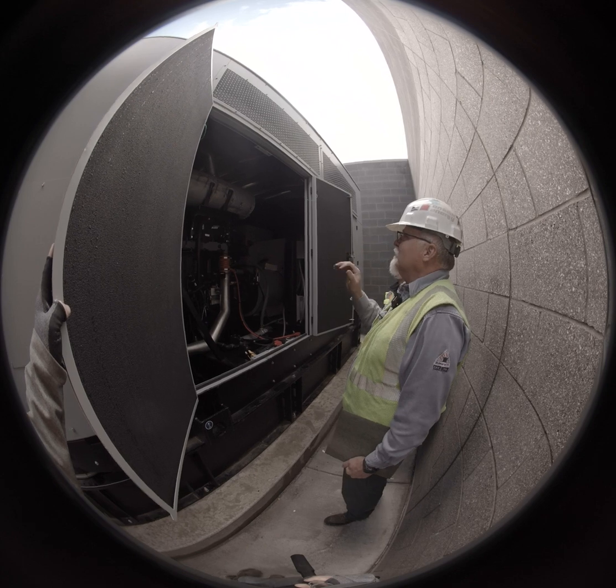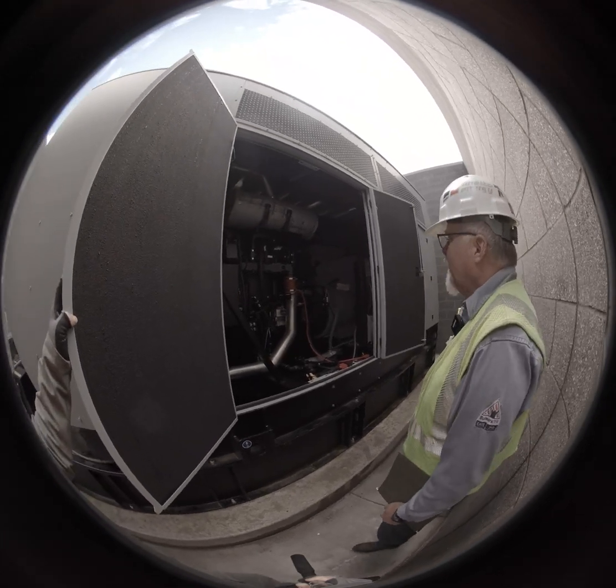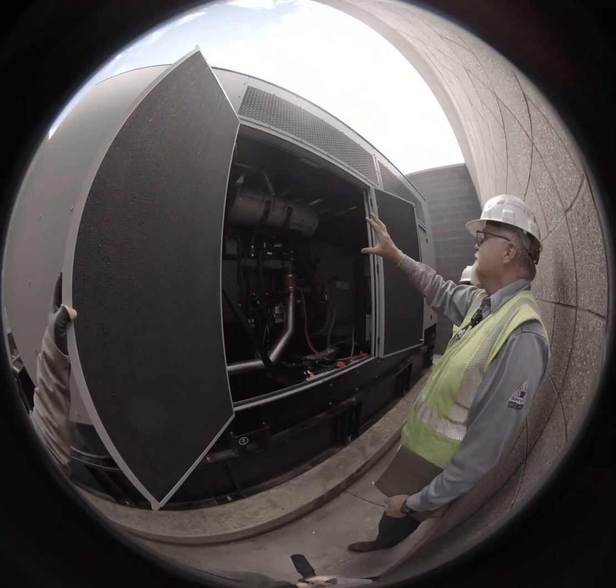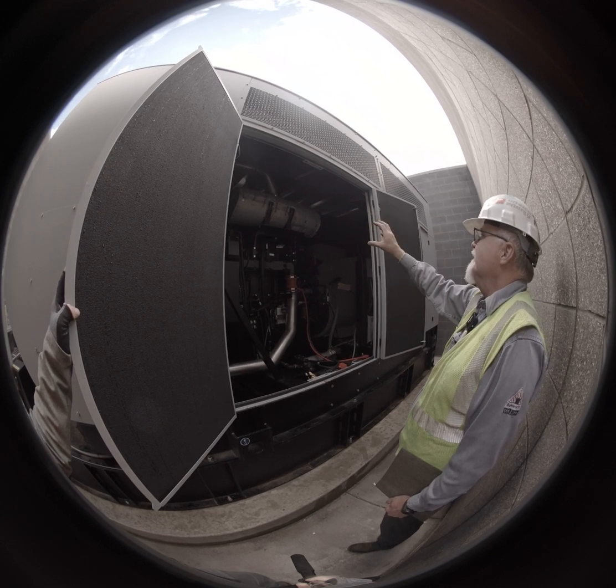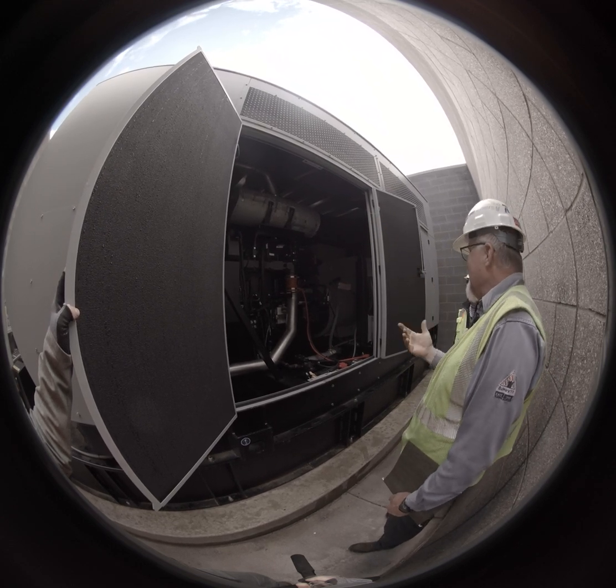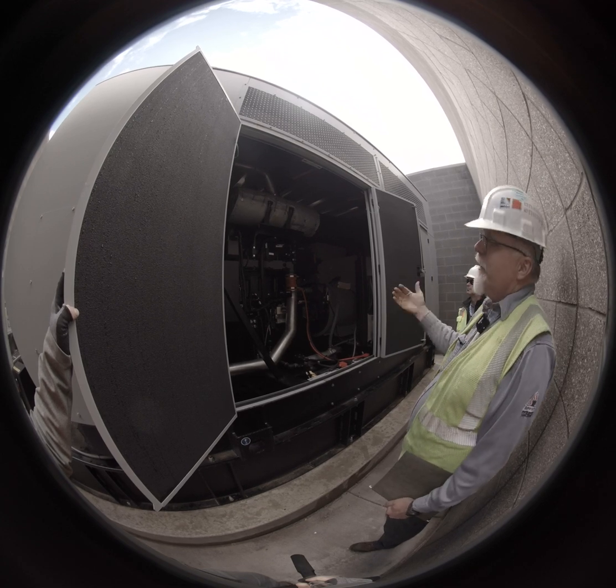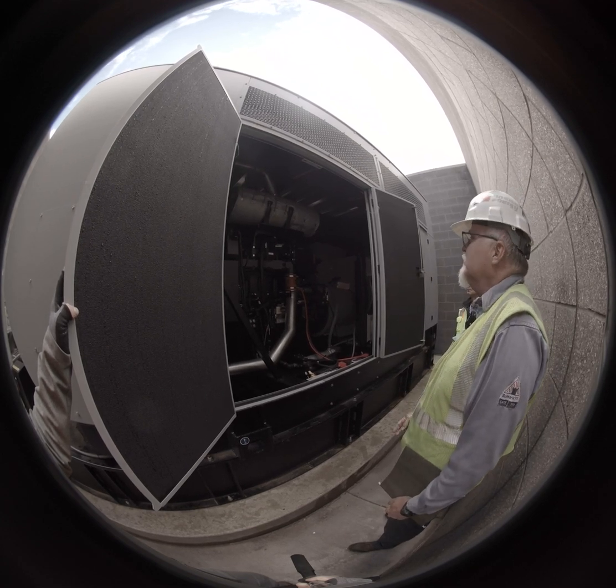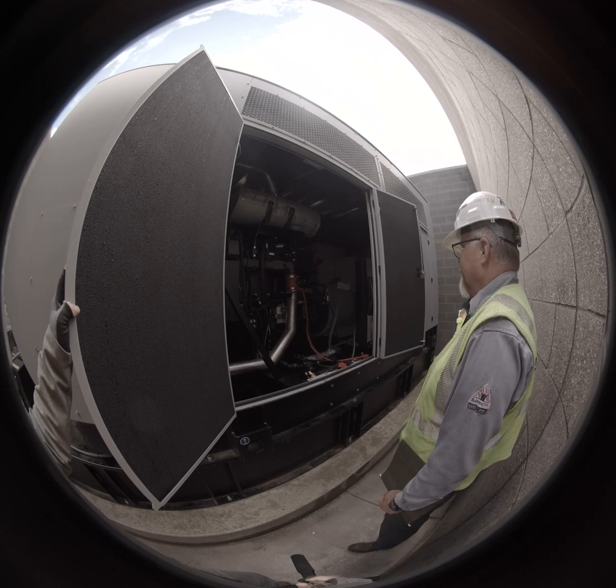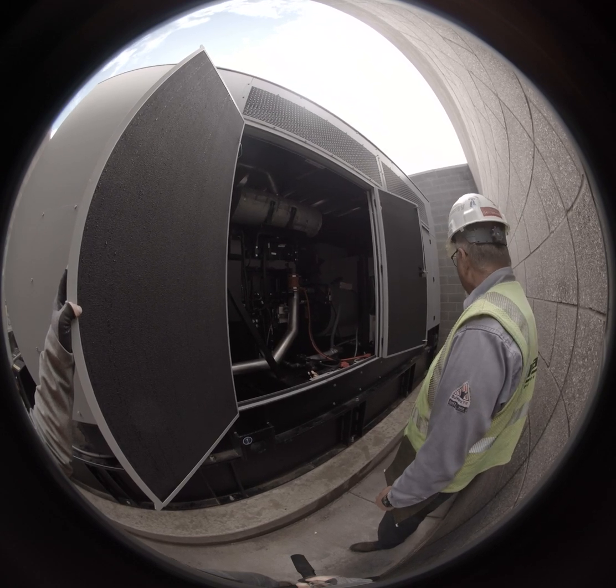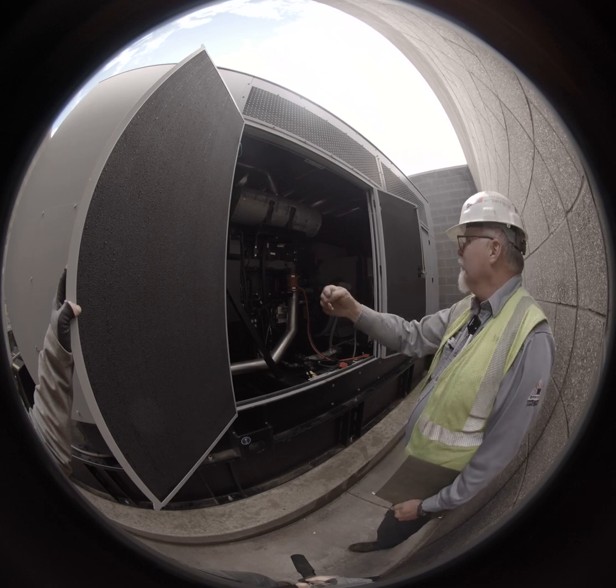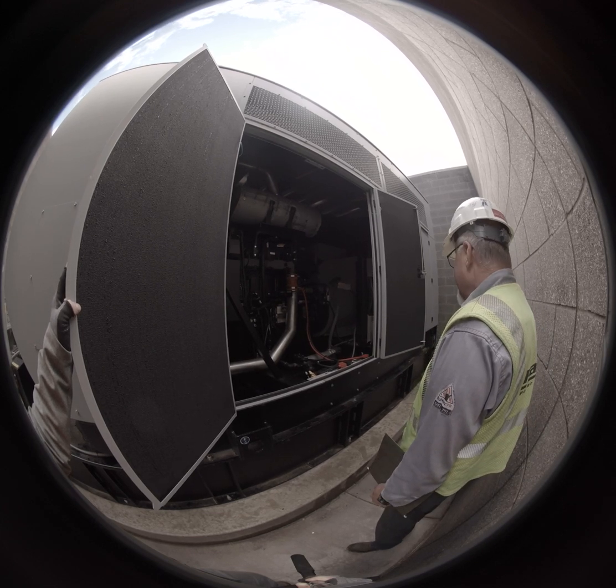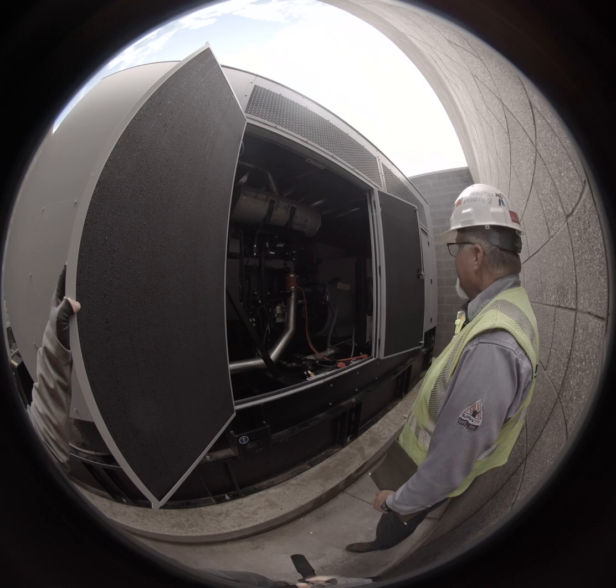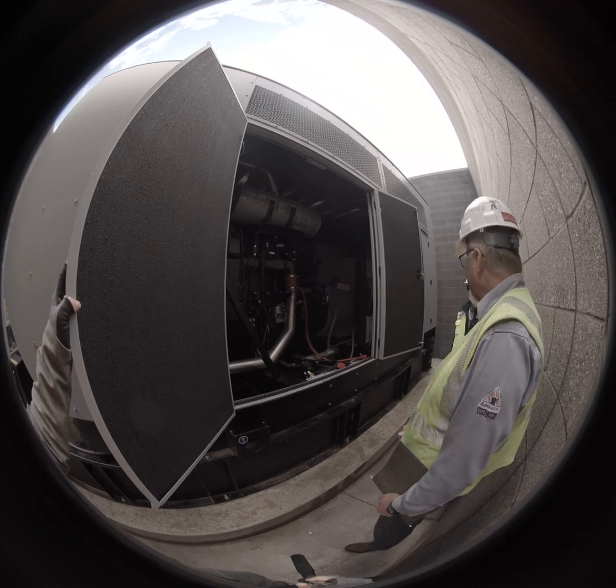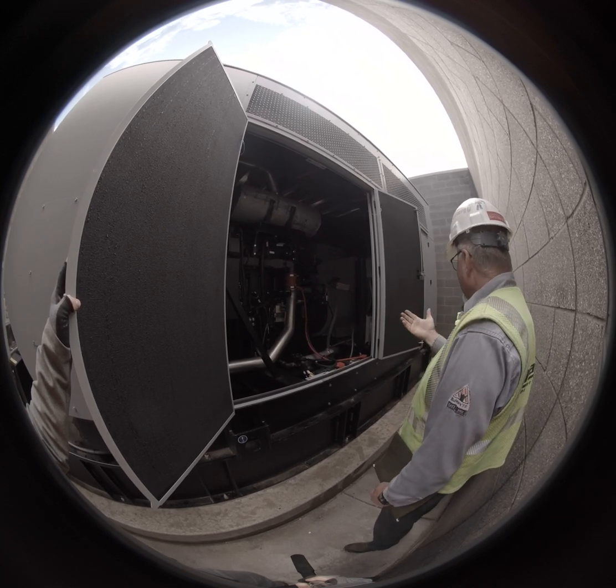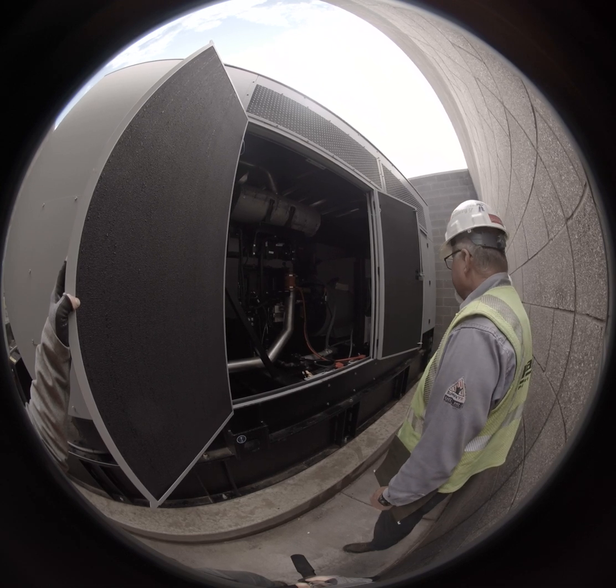Okay, so this is our John Deere engine. As you can see, we've got a lot of heat blankets and stuff like that, so we can keep the heat out of the enclosure because we don't want to add more heat shoving through the radiator. Gensets, typically, about 90 some odd percent of them, will push air out through the radiator. It's more efficient than pulling the cool air in. So it pushes it out. It has a turning hood on the front with sound baffles inside or sound foam inside to quiet the machine down.